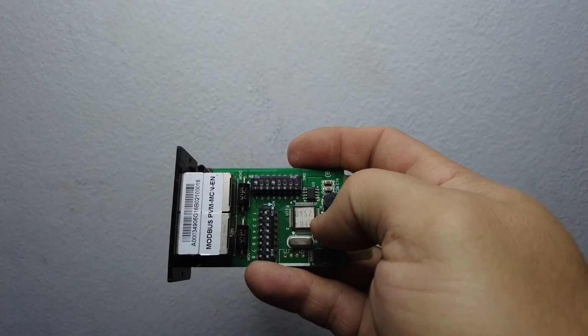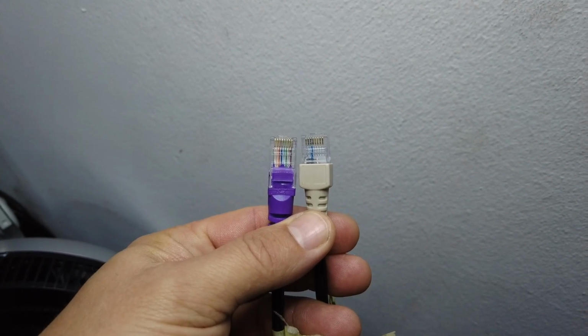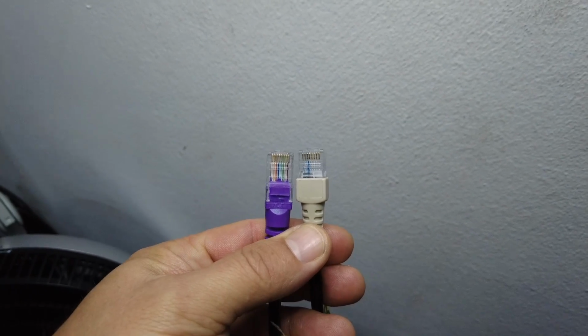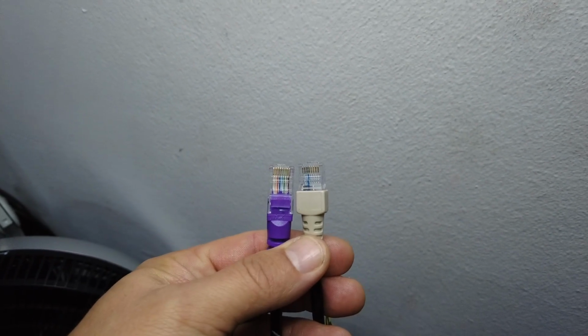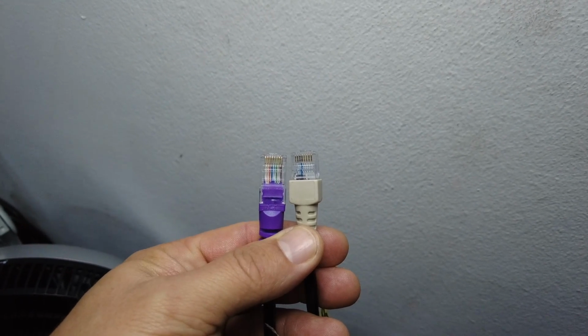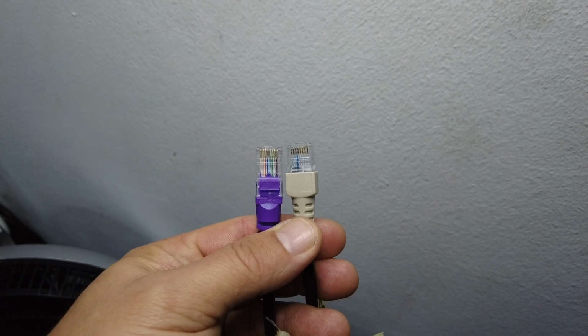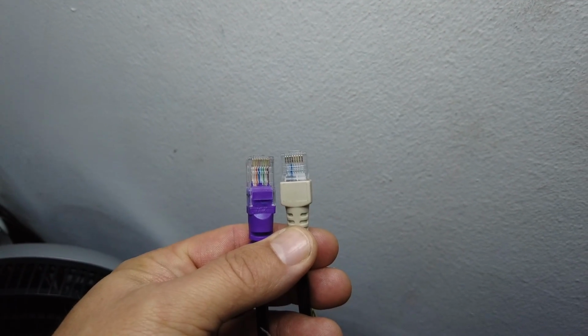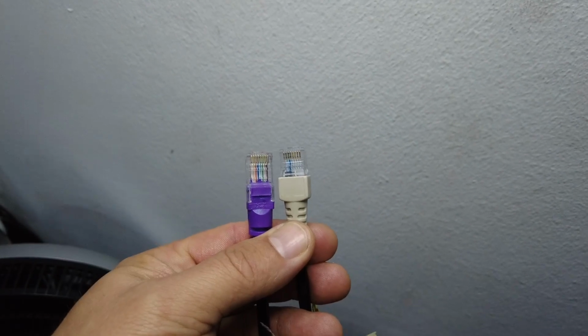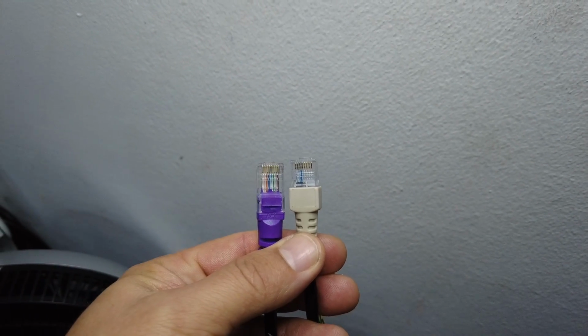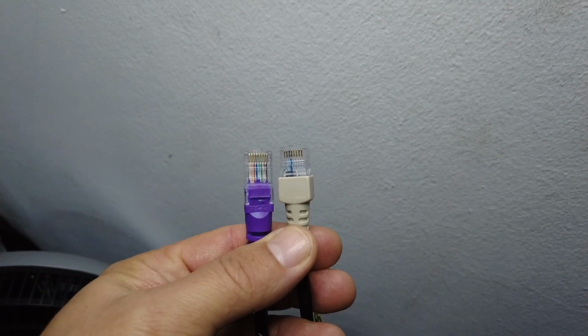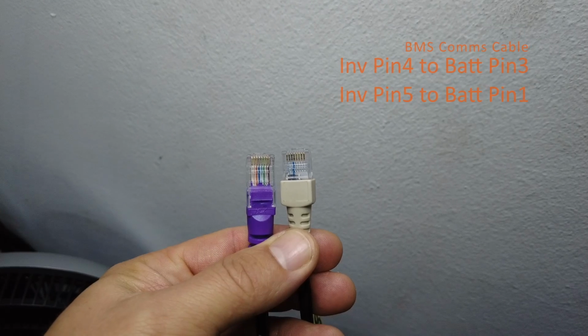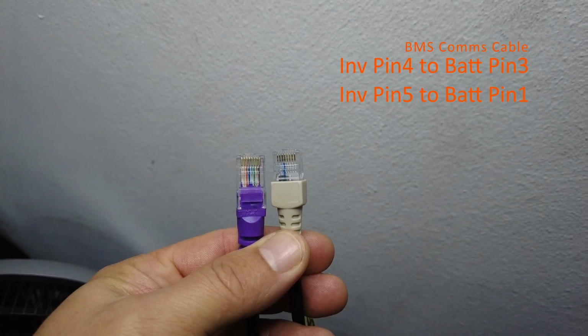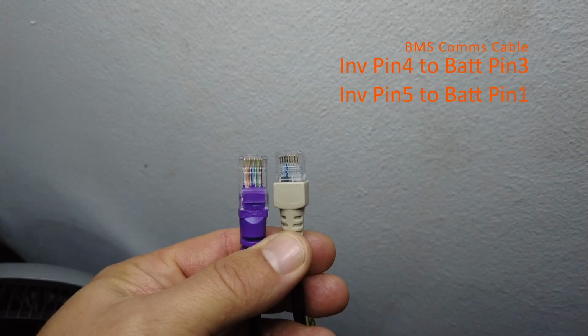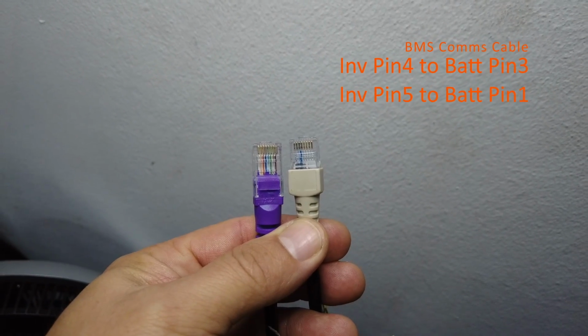For the BMS communications cable between the inverter and the battery, we need to make up the following cable. The plug to the left, the purple plug, will be the cable I'm using for the inverter, and then I've crimped a plug to the right for the battery. Inverter side, or shall I say BMS Modbus card, pin number 4 will go to battery side pin number 3, and then Modbus card side pin number 5 will go to battery side pin number 1.